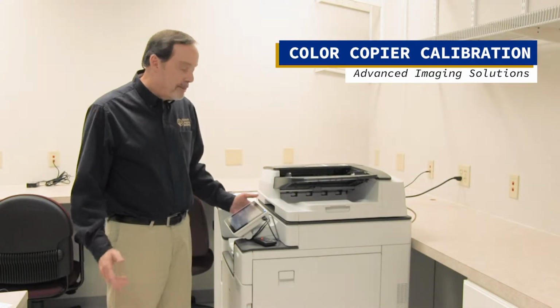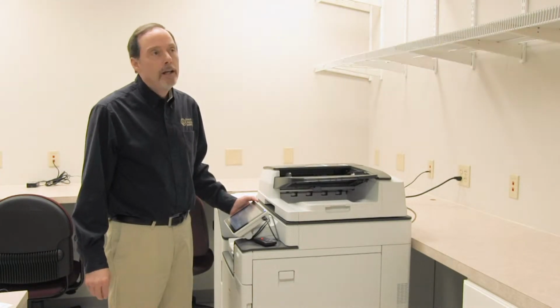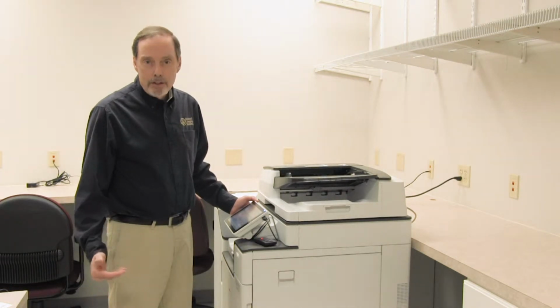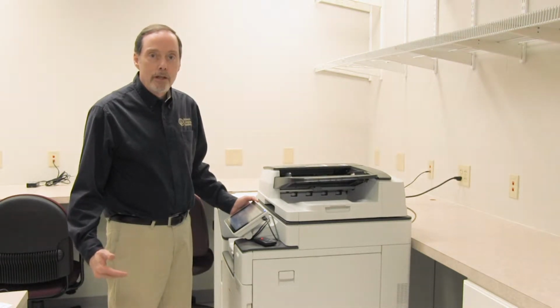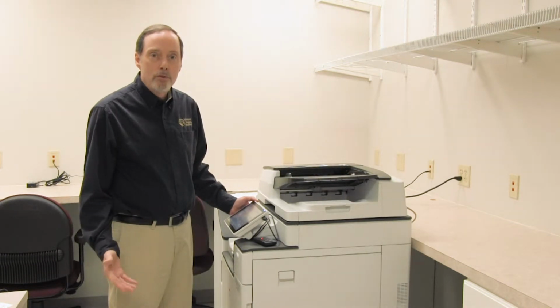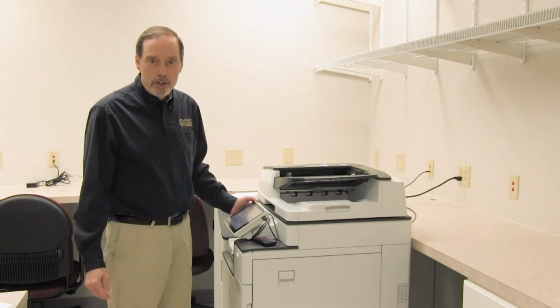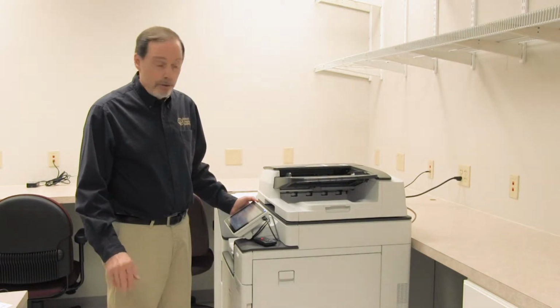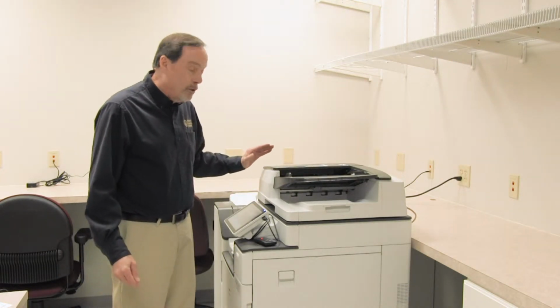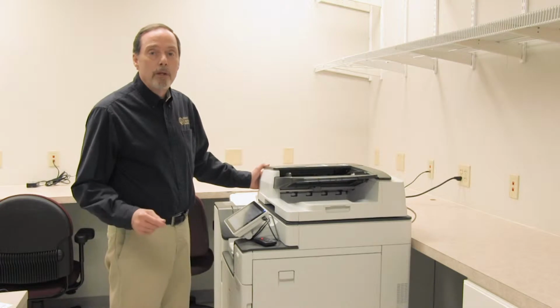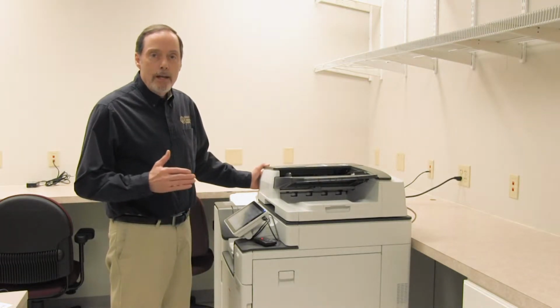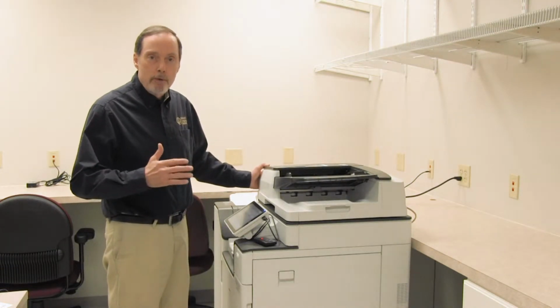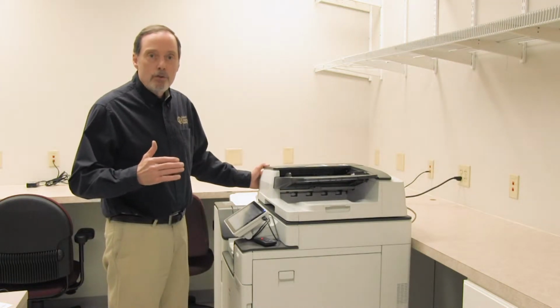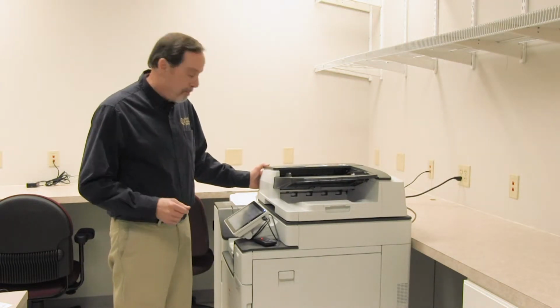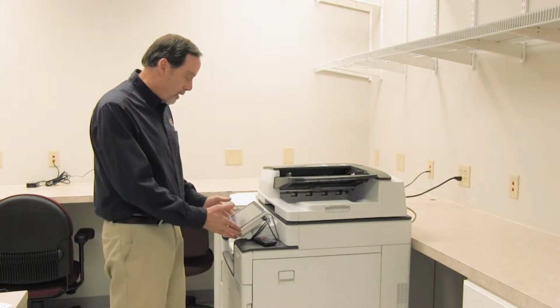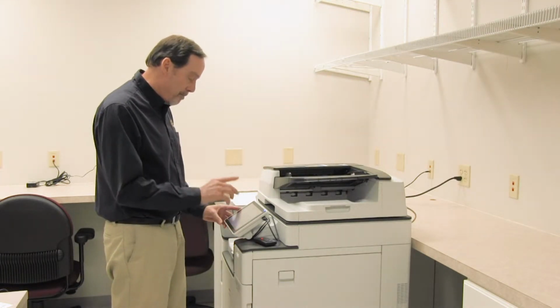We're going to go through the process today of how to calibrate a machine. As the in-house technician, I set up all new devices, and with every new device that comes in, we always run the auto color calibration in order to zero out the colors. It's a good idea to do this. All color devices have a tendency to want to drift from their original calibration, so we recommend that you do this once a month.